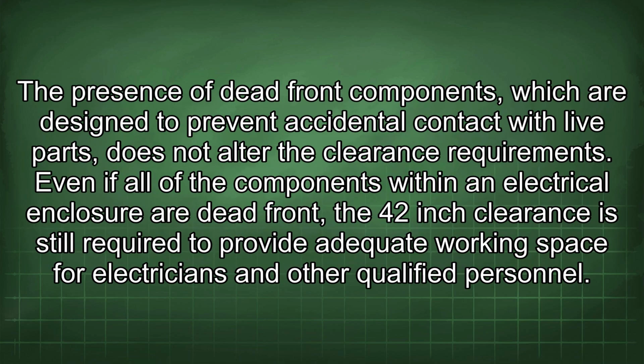The presence of dead front components, which are designed to prevent accidental contact with live parts, does not alter the clearance requirements. Even if all of the components within an electrical enclosure are dead front, the 42-inch clearance is still required to provide adequate working space for electricians and other qualified personnel.